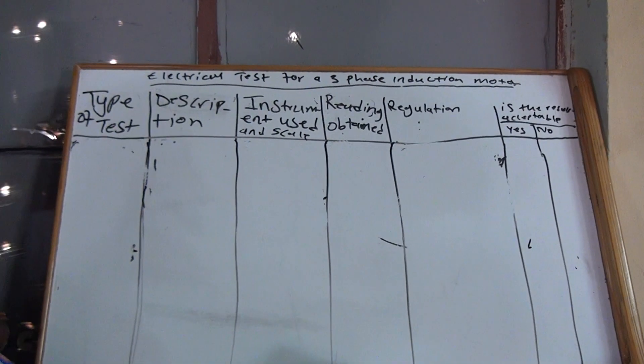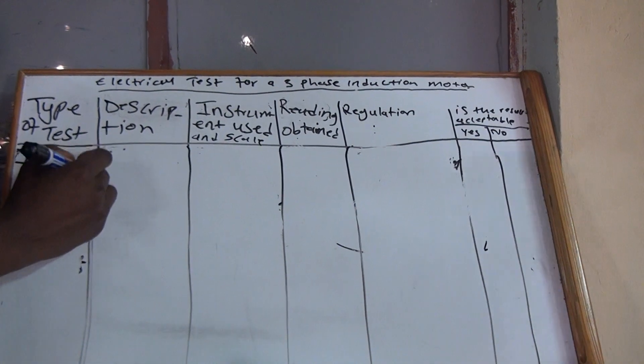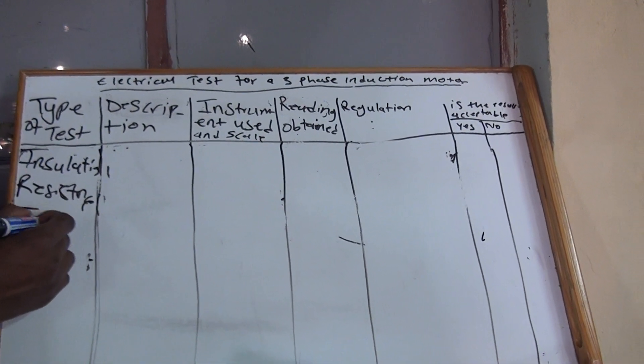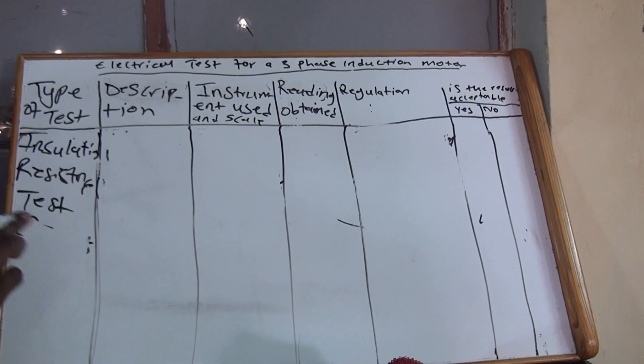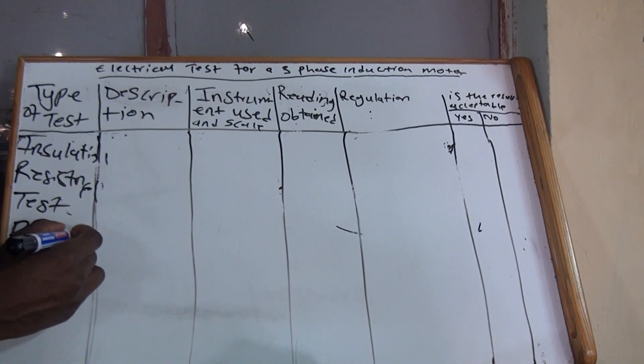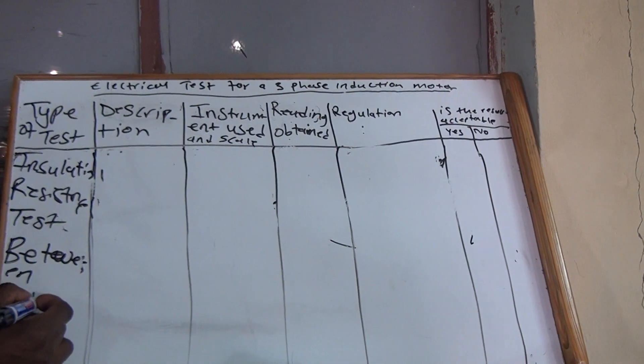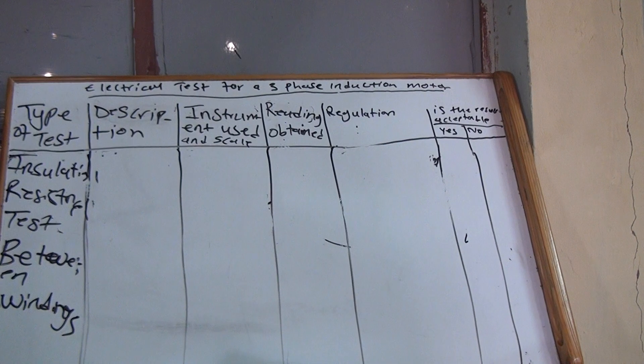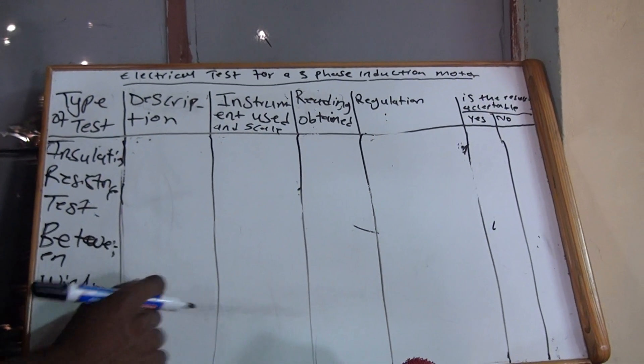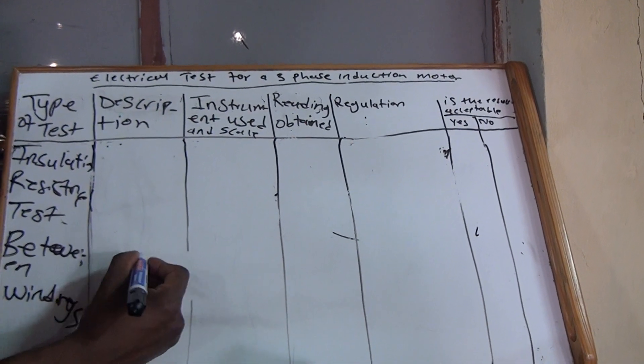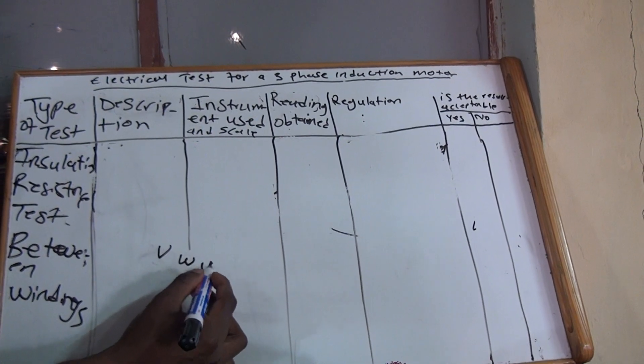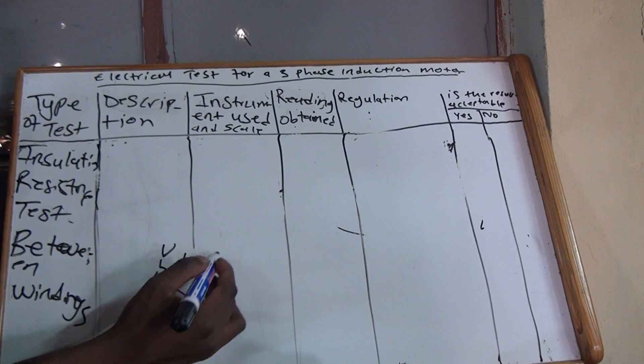The second test is the insulation resistance test between windings. On the description, write the actual points you are going to measure. I use U, V, W as a guide — so the pairs will be V1 and W1, then V1 and U1, and then what's left is W1 and U1.